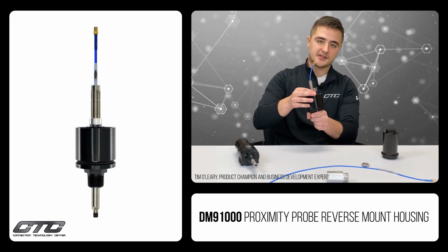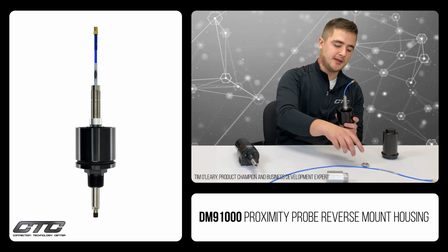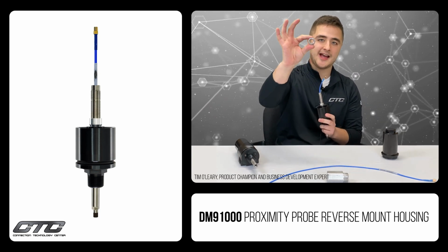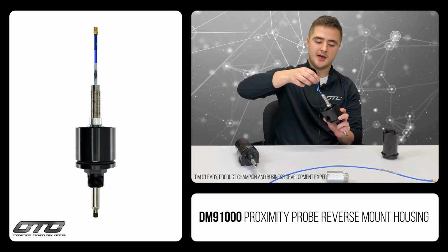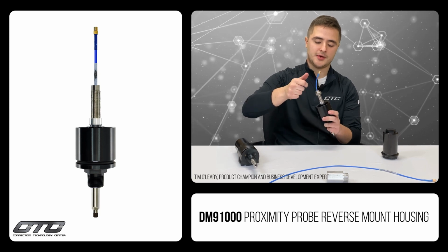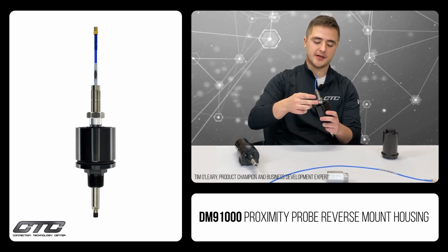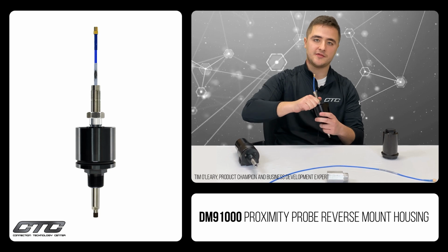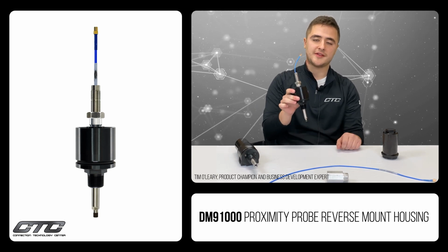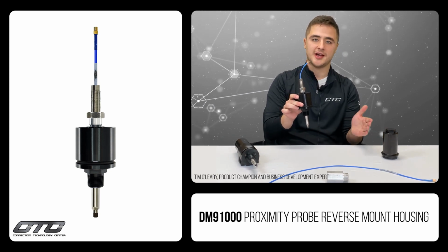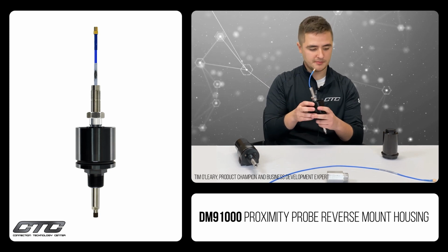That will lock the sleeve to your desired gap setting, and after that you will take the hex nut of the housing and screw that right on top of the sleeve nut. That hex nut will lock that sleeve nut into place, and it will make sure that the gap of your probe does not change while you have this housing installed.